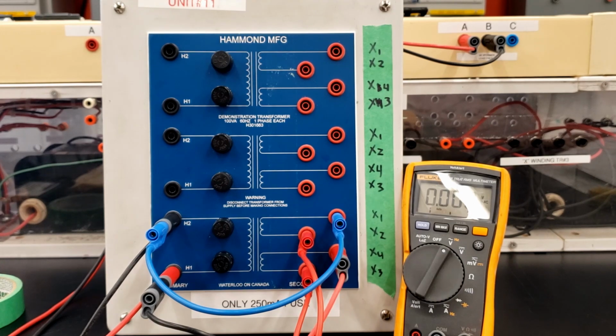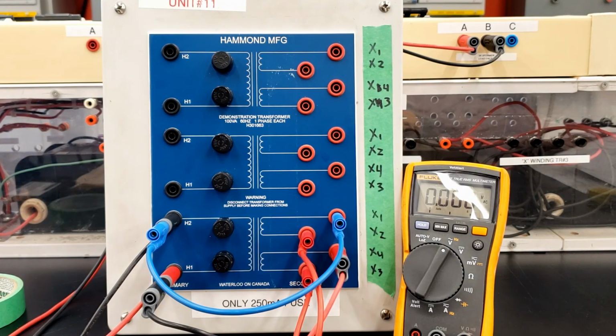Okay, sweet. Now that we've done all these connections, we should be able to create a 3-phase bank, and all of these transformers will be in phase. So we've taken all this time to make sure that all of the windings' magnetic fields are going in the same direction. That way, once we create a 3-phase delta or a 3-phase Wye, then we're going to have the appropriate voltages.